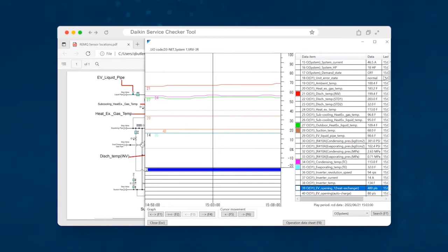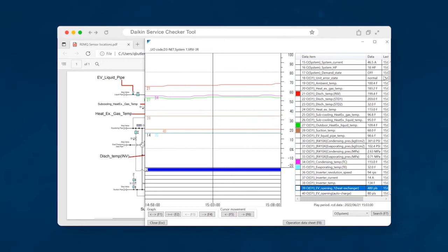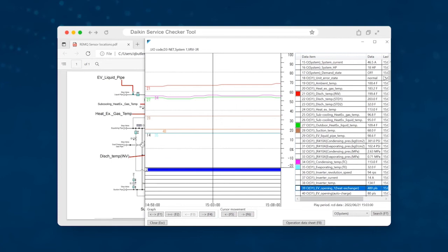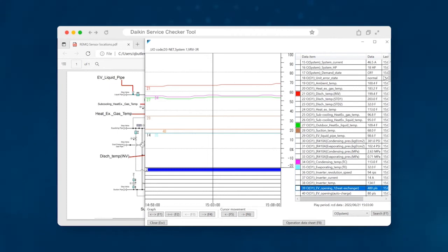That's the best way to do it. Same refrigerant back in or do you go with a fresh charge? We never do, especially on sites where it's a new customer. You have no idea what's been done to that system. You have no idea how the vacuum was pulled. You don't know if the proper procedures were followed. Refrigerant is getting more expensive, but it's always the safest bet to just go ahead and change that refrigerant. You know that the system's clean. Know that it's tight. Know that it's dry. It's still not more expensive than labor and expertise. You're absolutely right. I promise you it'll be cheaper than one compressor replacement.